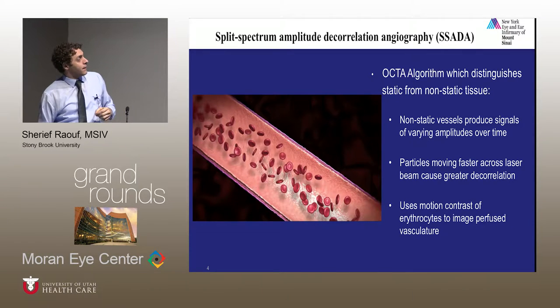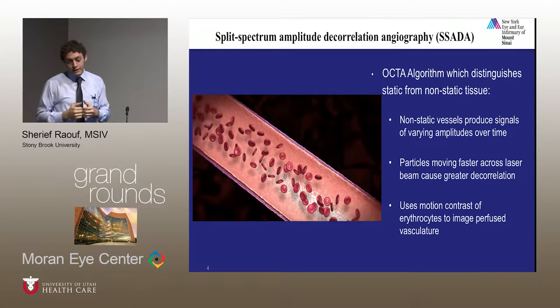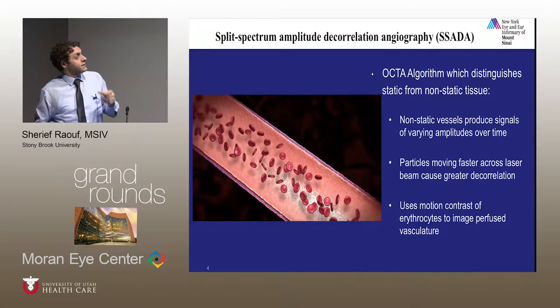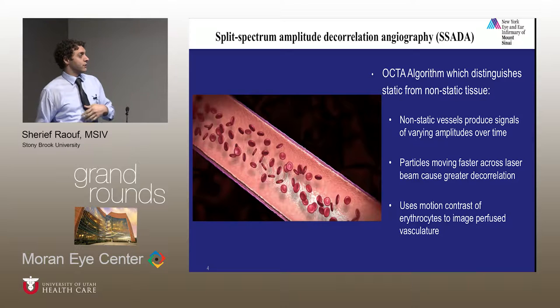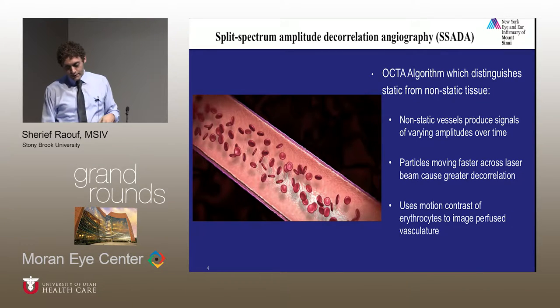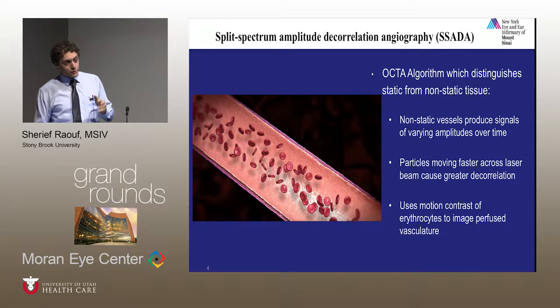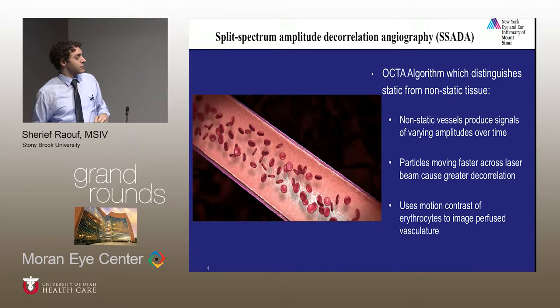The technology that distinguishes OCTA from OCT is called split spectrum amplitude decorrelation, or SSADA. It allows the machinery to distinguish between static and non-static tissue, because non-static vessels produce signals of larger or more varying amplitudes over time. Particles moving faster across the light beam will cause higher decorrelation, allowing perfused vessels to be distinguished from more static tissue.